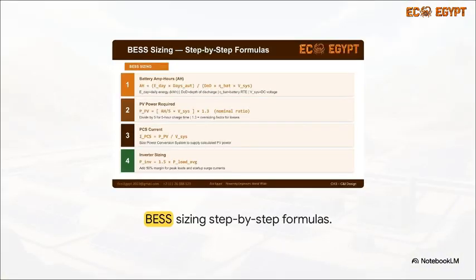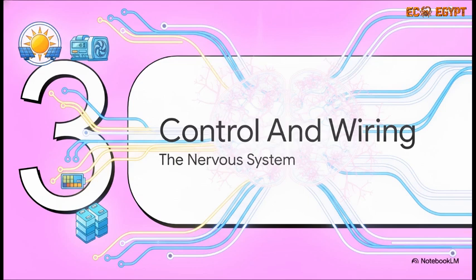Next up in our sizing steps, we calculate the BESS, the Battery Energy Storage System. Looking at the exact engineering workflow here, first you determine your battery amp hours based on daily energy and depth of discharge. And by the way, lithium-ion LFP batteries are the industry standard here for their thermal stability. Once you lock in that capacity, you calculate your required PV power using a 1.3 nominal ratio for system losses. Finally, you size the power conversion system and your grid-connected inverters, usually adding a 50% margin to handle peak loads without tripping. All right, Section 3, hybrid control and wiring.